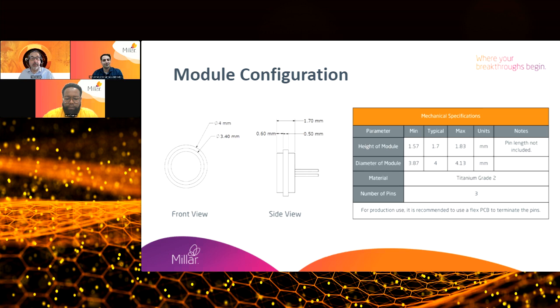All right, next question. Let's see. I'm going to combine a couple. We have a question, what is the temperature range of the TiSense? But there's also a question higher up from Ben. I am curious, the operational temperature is 35 to 39 degrees. What if a patient has a high fever? So, Mohammed, could you give us a little sense of that? Yeah, that's a really good question. So the TiSense modules are primarily designed to have an optimum performance around the standard body temperature range, which is about 35 to 39, as you mentioned.